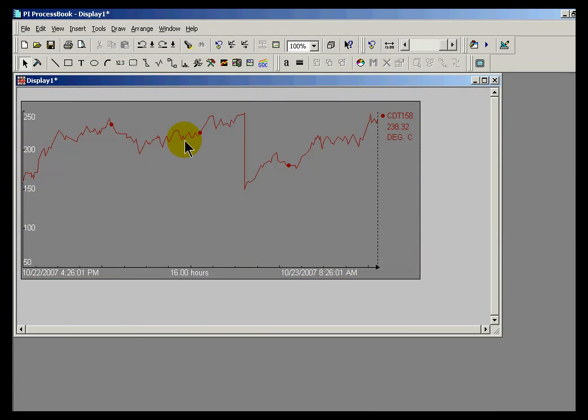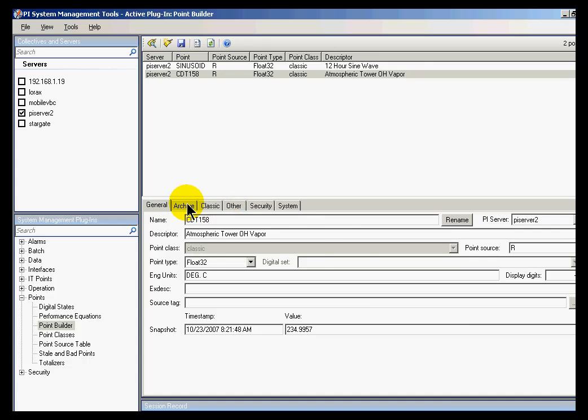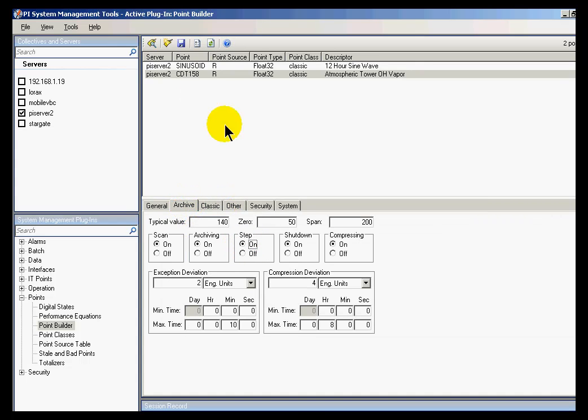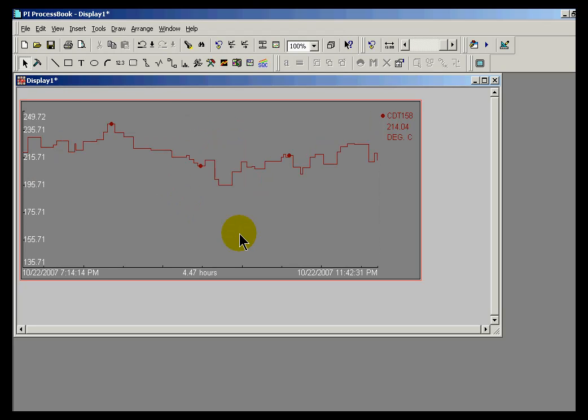Let me show you a tag definition. This is the tag CDT158. If we look at the actual display of that, here's what it looks like with Step turned off — we're connecting the dots between the actual archive values. Now if I go into the Archive section, set Step equal to On, and save this, within a few seconds ProcessBook picks up that change and starts displaying this as a stair-step function instead of the traditional connecting-the-dots function.